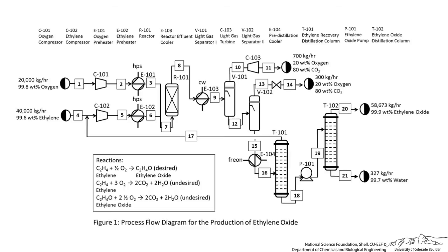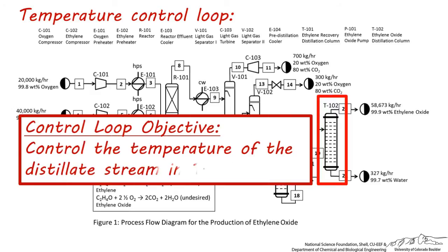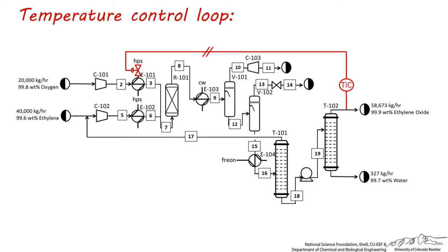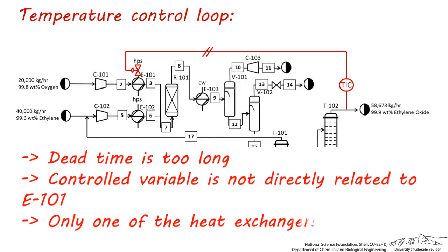Let's look at another example, this time of an improperly designed temperature control loop. Let's say we'd like to control the exit distillate temperature from T102. Here's one example of how we might do this. What's wrong with this control loop? You obviously want to try to avoid a control loop like this, where the dead time is too large, the exit temperature is not directly related to the heat exchanger attempting to control it, and only one of the parallel heat exchangers is being controlled.